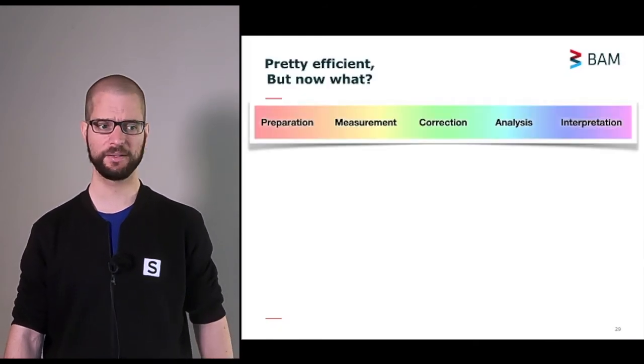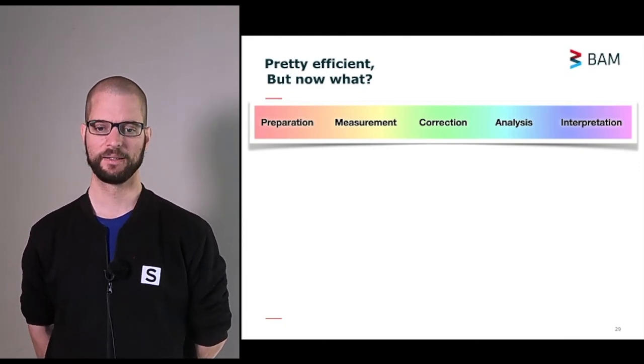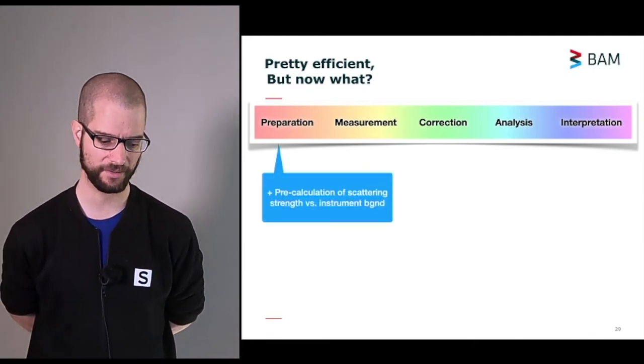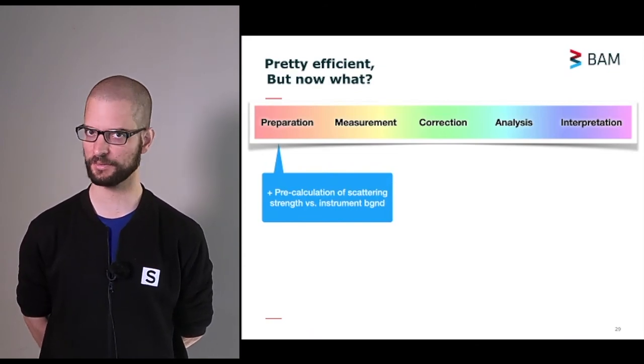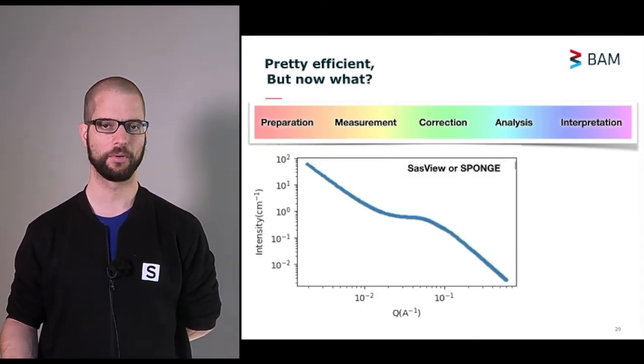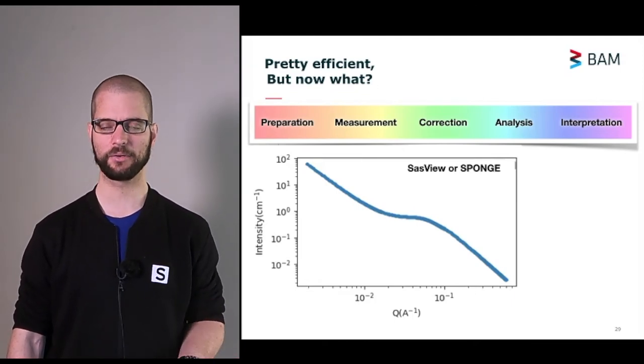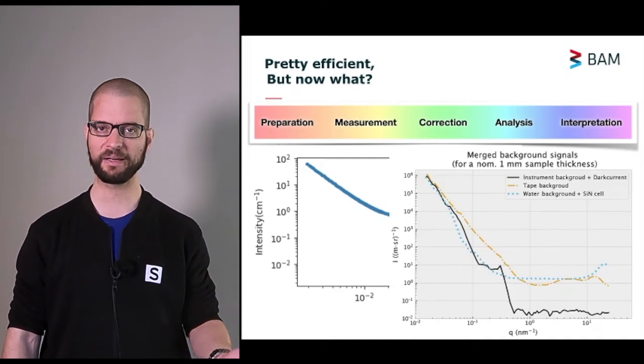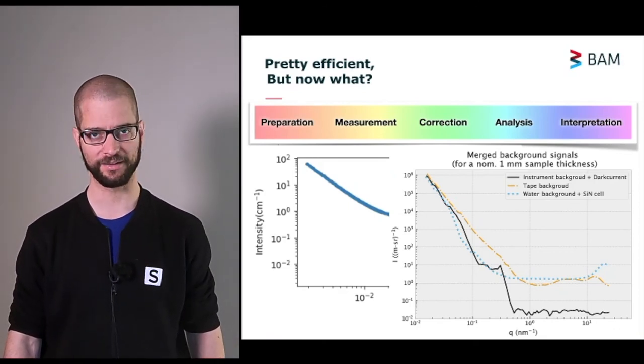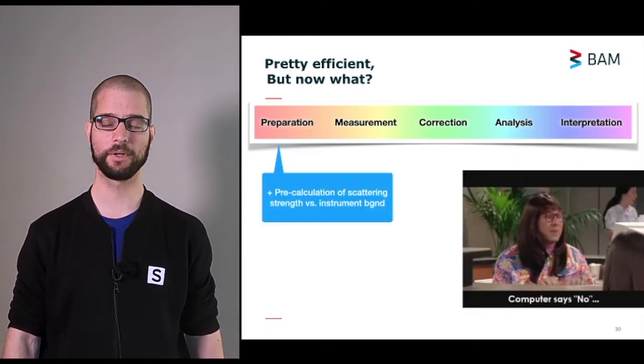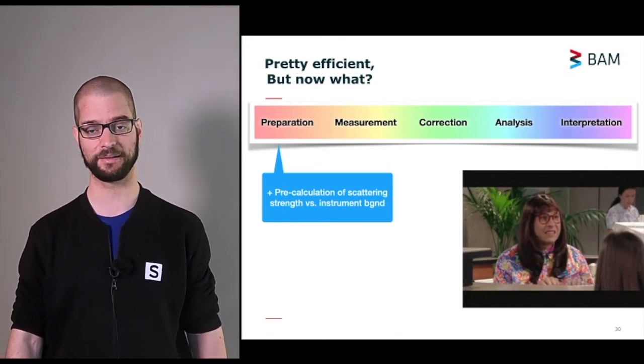Alright, so that is pretty efficient. We're not completely done yet. We've done a lot, but we're not completely done. There's always more to do. For example, we would like to be able to assist the design of our experiments by pre-calculating scattering patterns in cases where we're not sure whether things are going to work. This means that we can use SASView or my program, The Sponge, to calculate scattering patterns in absolute units and compare these calculated scattering patterns with the background levels of our instrument. And then we can immediately see whether we will get a good signal-to-background ratio, whether it's worth trying these experiments on our machine. If not, we can tell in advance that maybe they can go to some of our colleagues with brighter sources or better signal-to-background ratios.